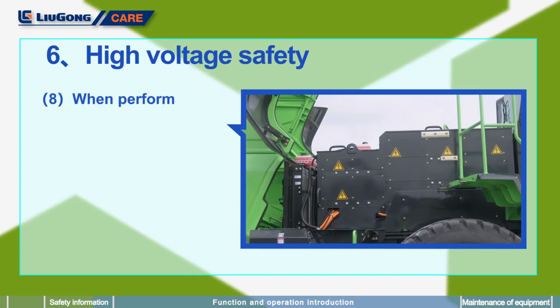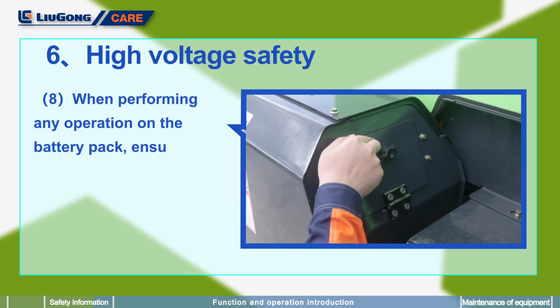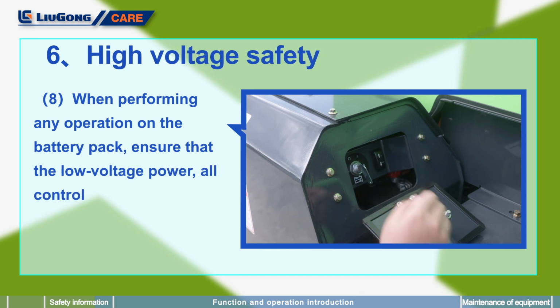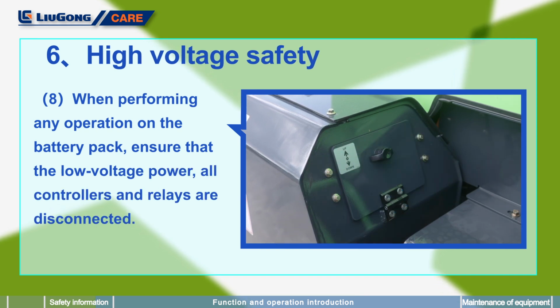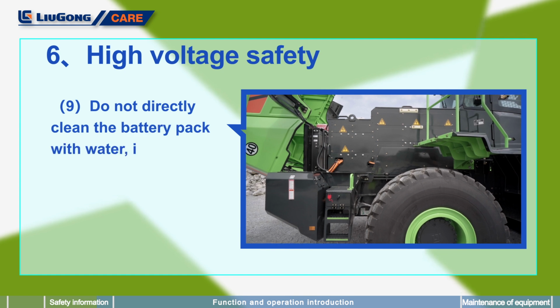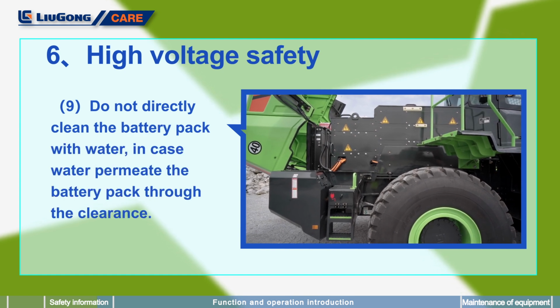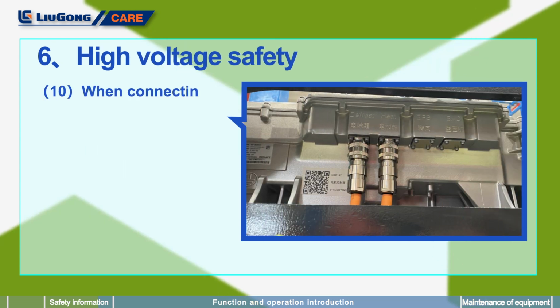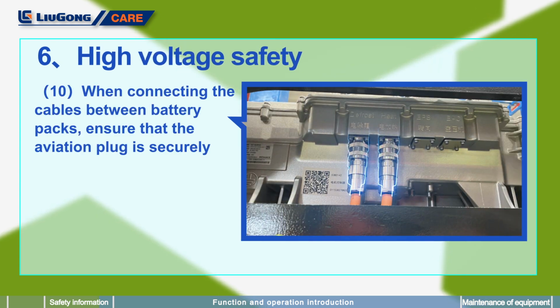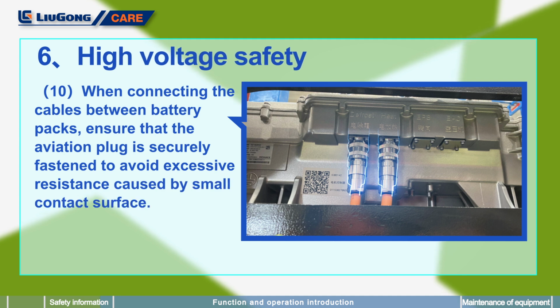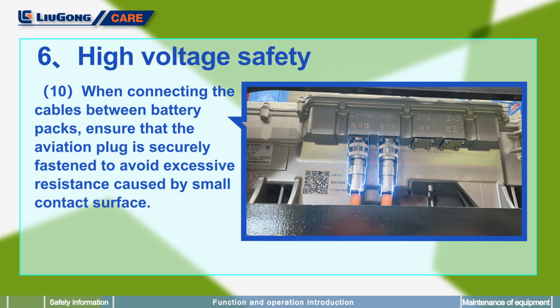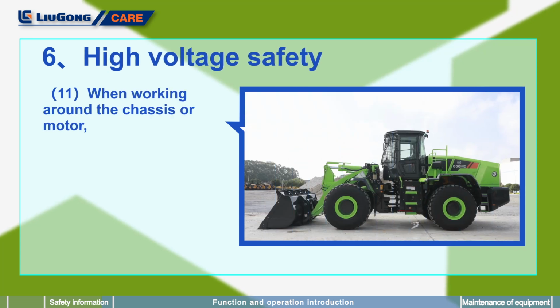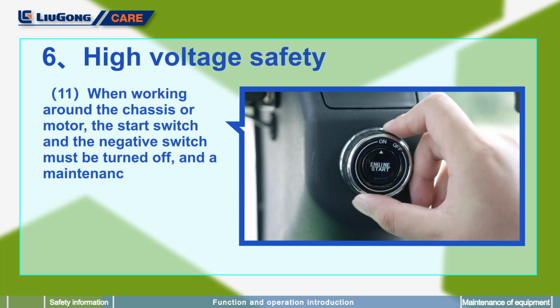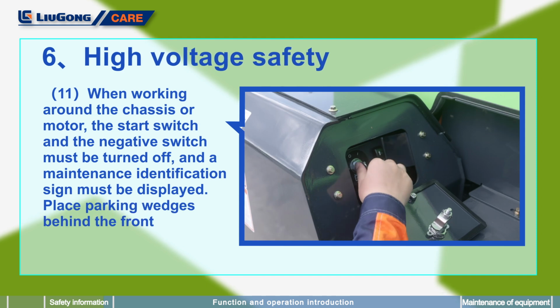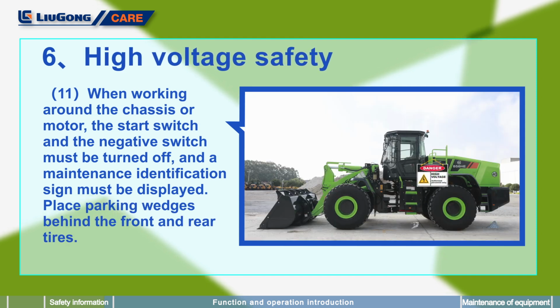When performing any operation on the battery pack, ensure that the low voltage power, all controllers and relays are disconnected. Do not directly clean the battery pack with water, in case water permeates the battery pack through the clearance. When connecting the cables between battery packs, ensure that the aviation plug is securely fastened to avoid excessive resistance caused by small contact surface. When working around the chassis or motor, the start switch and the negative switch must be turned off, and the maintenance identification sign must be displayed. Place parking wedges behind the front and rear tires.